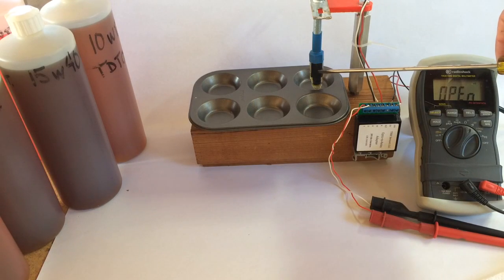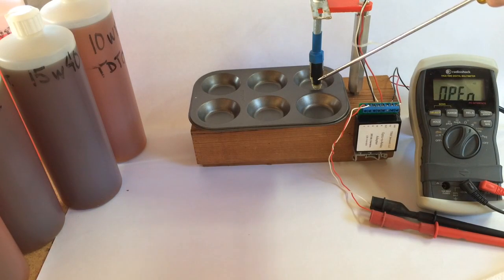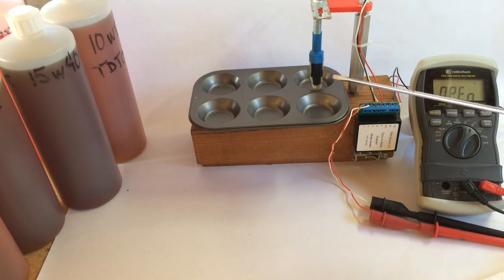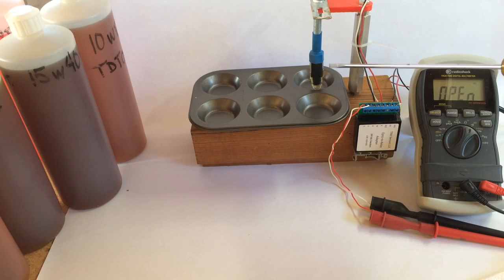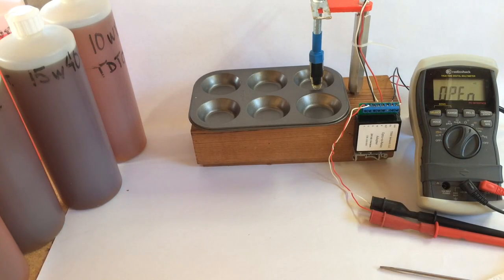This is the actual optical probe. It's manufactured by TRM Sensors. It has a little clear plastic nose cone. That's the actual sensor portion. The way it works is by sending a beam of light from inside the sensor body. It's refracted by the plastic nose cone and detected by a photodiode inside the body of the sensor. As long as there's nothing but air around it, it doesn't cause any response. But if you put water and oils that we'll be testing today, the light is scattered and does not reflect back internally, and the sensor goes into alarm.